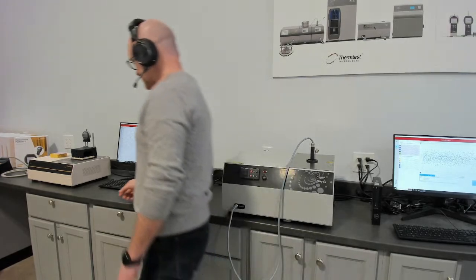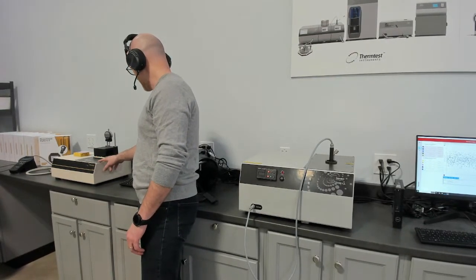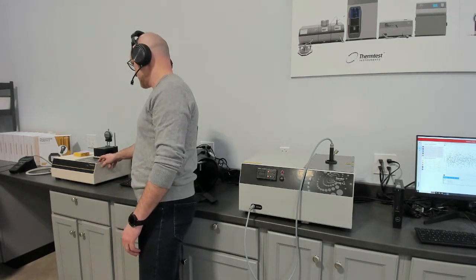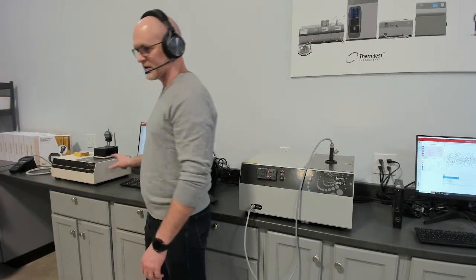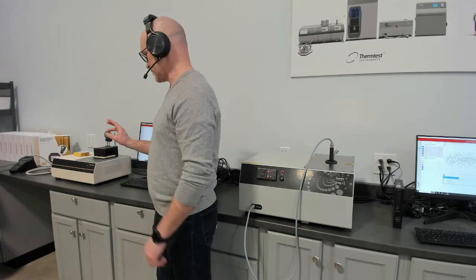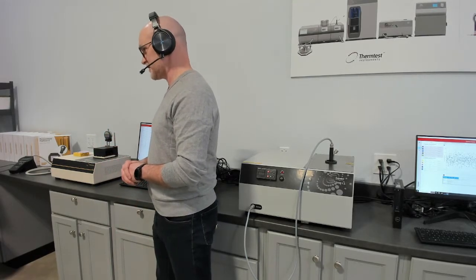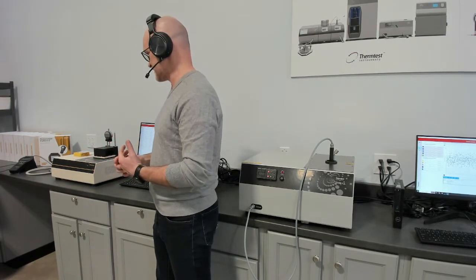The baby brother to the heat flow meter series is our HFM 25, and this is designed for measuring small format insulation materials from 2 millimeters up to 25 millimeters thick. The sample size can be as small as 2-inch square.